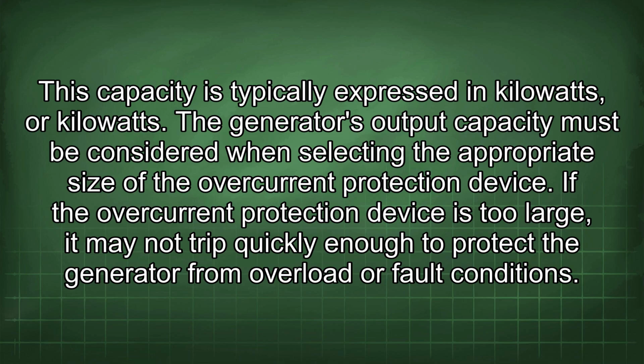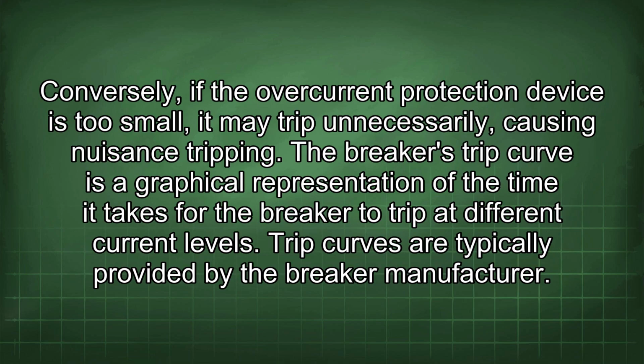If the overcurrent protection device is too large, it may not trip quickly enough to protect the generator from overload or fault conditions. Conversely, if the overcurrent protection device is too small, it may trip unnecessarily, causing nuisance tripping.